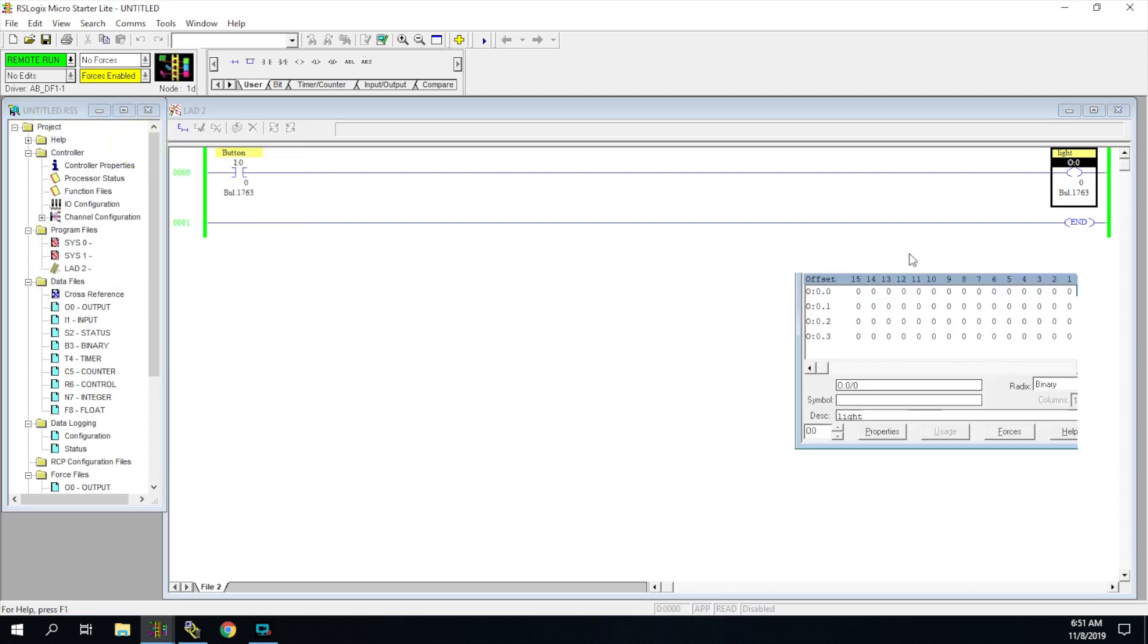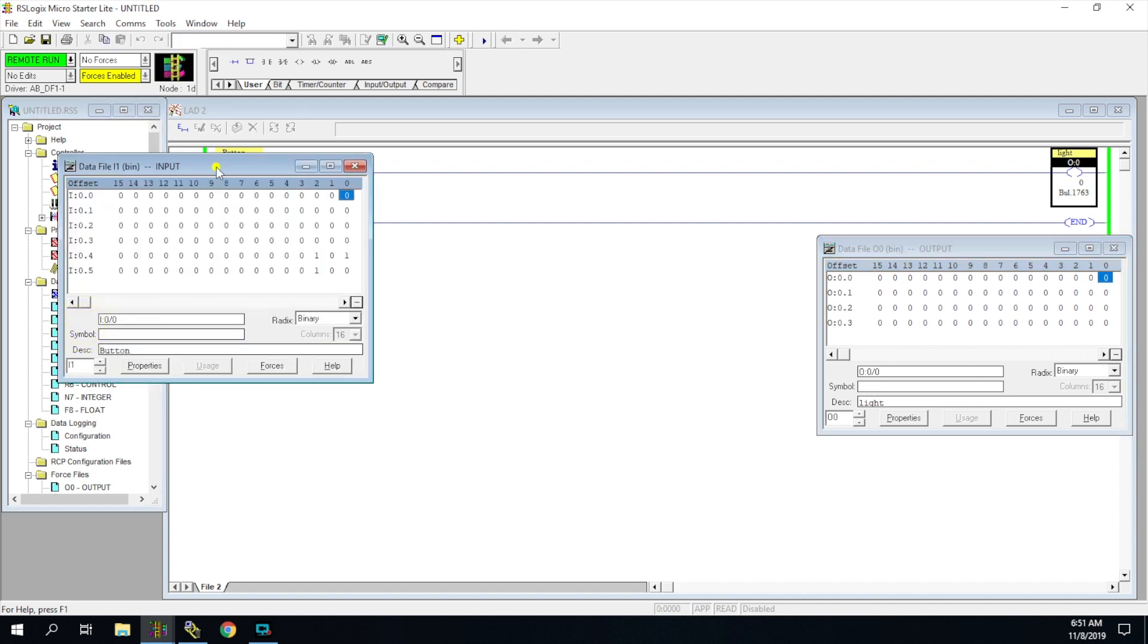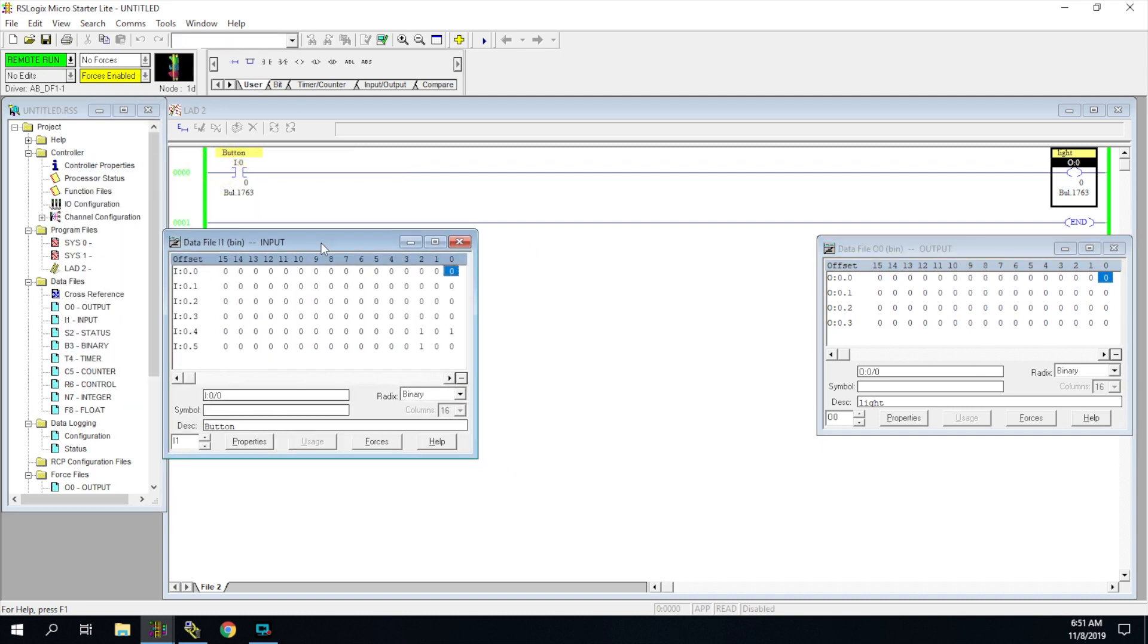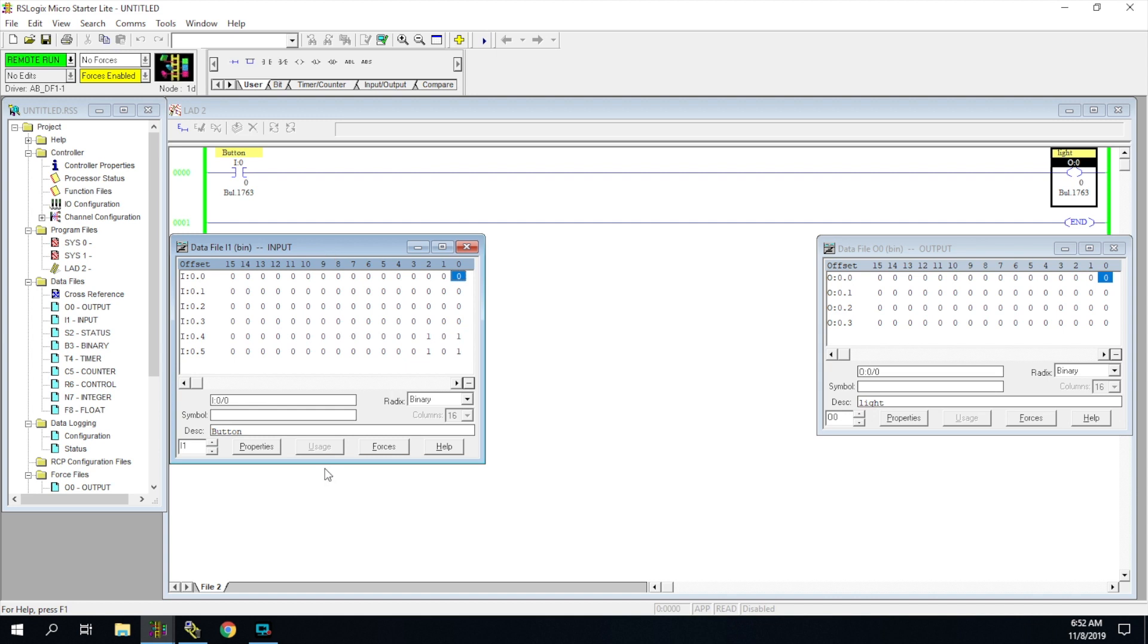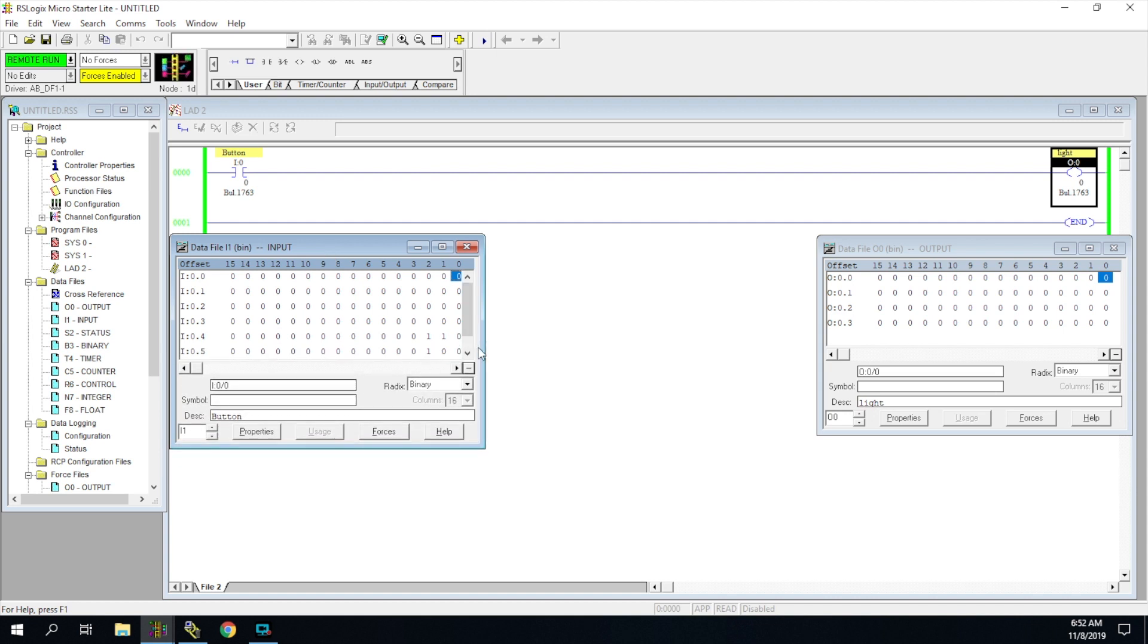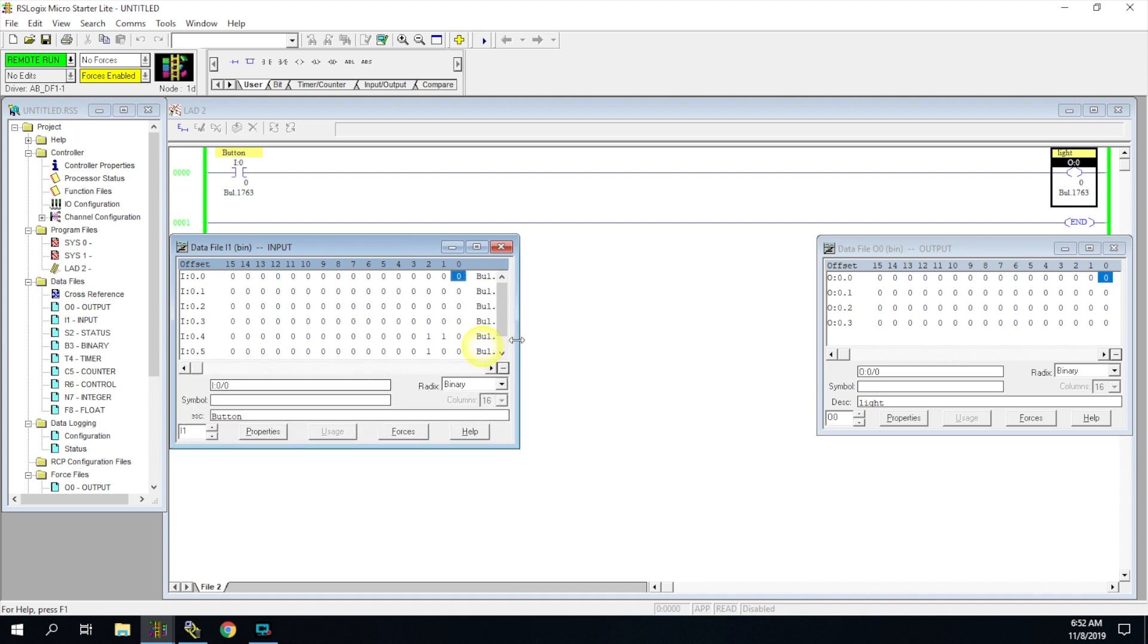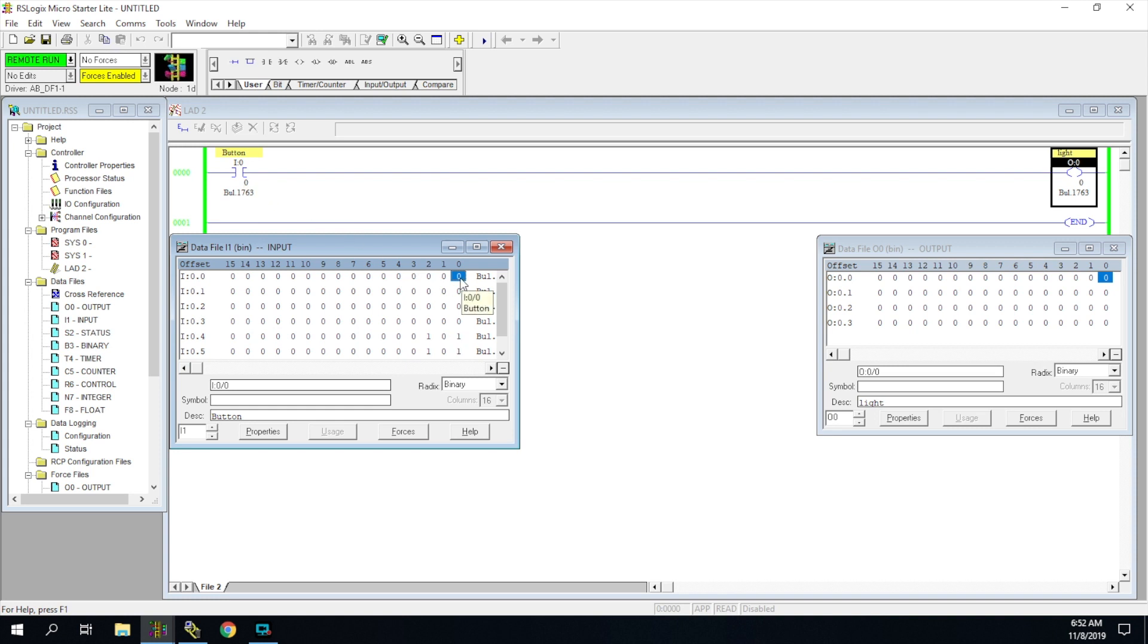So we got our data file for our output and our data file for our input. Now previously I talked to you guys a little bit about the bits. Well, these are actually our internal bits right here for all of our inputs, and here are our bits for all of our outputs. Now I am running right now, so that means when I press the button this instruction will become true. I want you to notice that the bit right here is also coded to the same instruction. So this instruction right here is this bit.